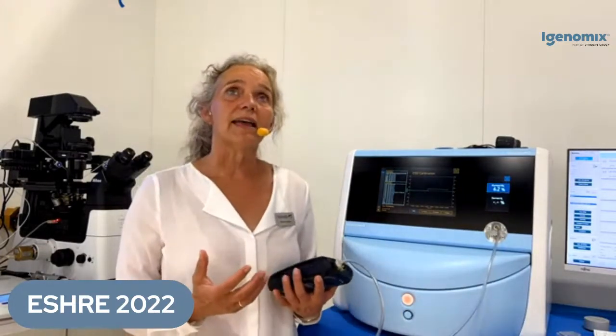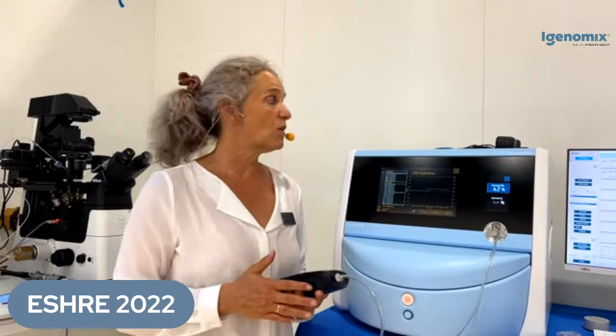So I think I'm going to continue with the O2, the temperature validation and calibration. And what I would say, actually, if you're using a reliable medium like GTL medium, we know that it's very stable. It's the same pH every time. So then just do your CO2 measurement on a regular basis. This is sufficient. But I will touch on the pH measurement in the end anyway, if you prefer to do that.